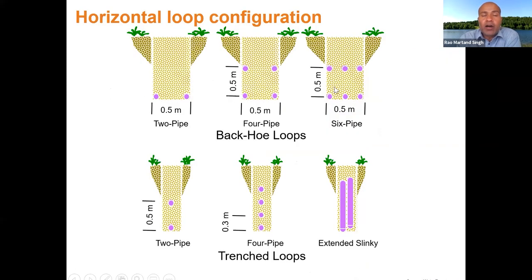Now let's look at the configuration, how do we place the loops? These are the various types of configuration used in a trench. This is for a horizontal loop, so here's only one loop, here two loops, here three loops placed vertically, here placed horizontally, and then the slinky type, which is a helical type. So there are various configurations used by industry, and the slinky or helical one is very popular because you get more length and more heat exchange.